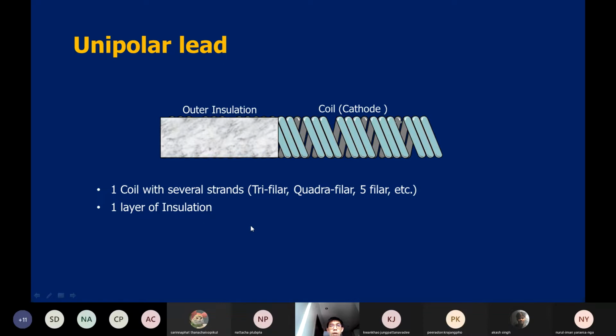This unipolar lead can only function when you connect it with the pulse generator, and the pulse generator is put inside the patient, because we need another electrode, which is the pulse generator itself. So the unipolar lead is the cathode electrode, and the pulse generator is the anode. We need both of them to conduct the pacing of the patient.